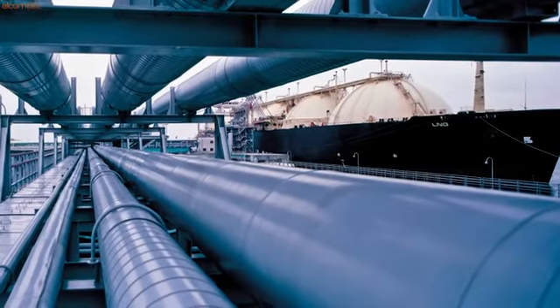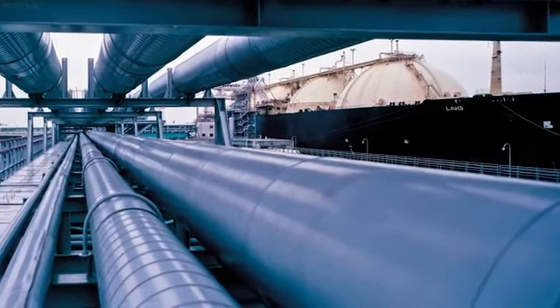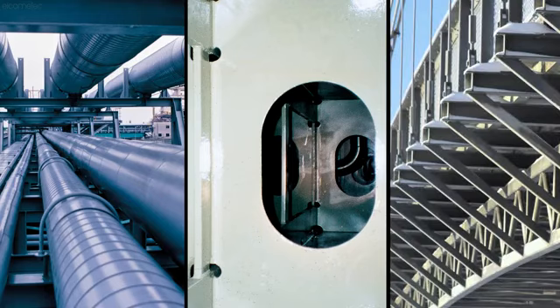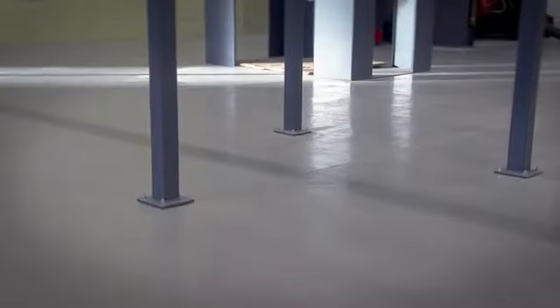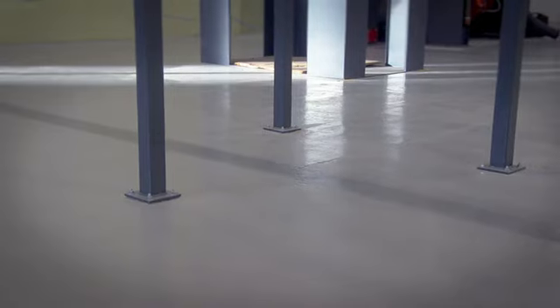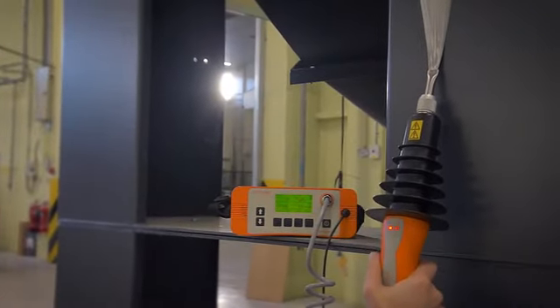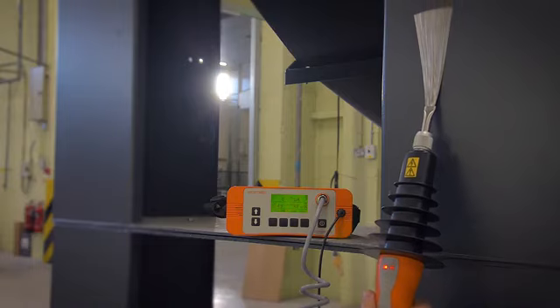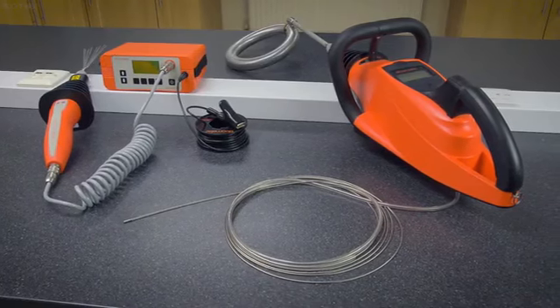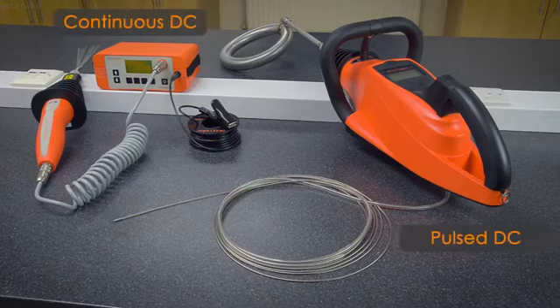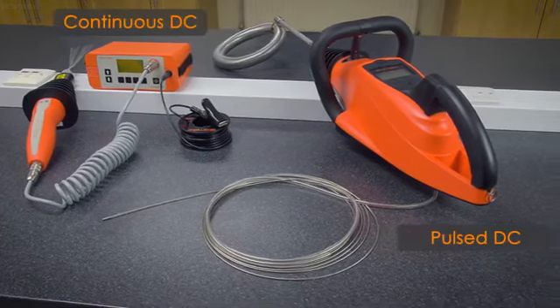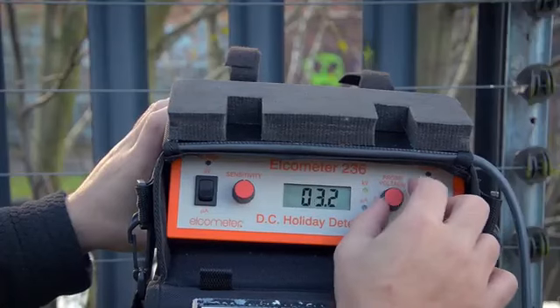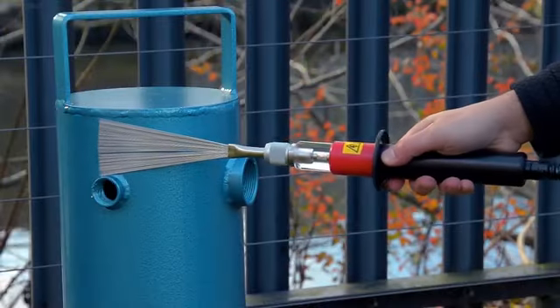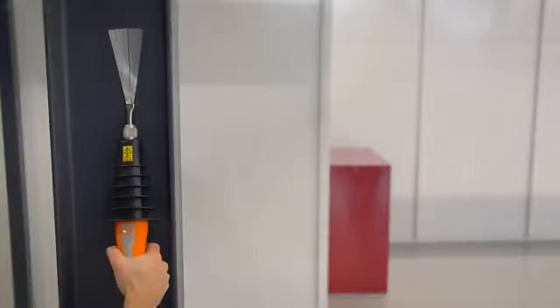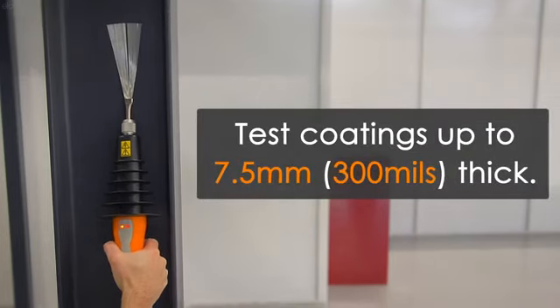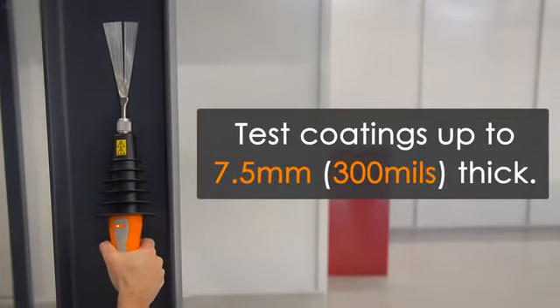When it comes to testing the porosity of protective coatings on pipelines, ballast tanks or bridges for example, or testing for flaws in coatings on concrete, typically the high voltage or holiday detection method is used. The high voltage method comes in two versions, continuous DC and pulse DC. In this video, we'll be introducing you to the continuous DC method, which is used to test non-conductive coatings up to 7.5mm or 300mils thick on conductive substrates.